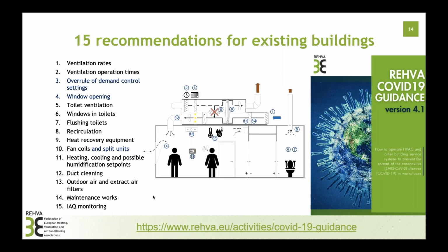REHVA has set out 15 recommendations, and these apply to the ventilation rates and how the ventilation is operated. Very many apply to the situation where you have a mechanical ventilation system, and in many countries this is implemented with heat recovery, and recirculation is not needed. That seems to be more of a European practice. But in the US, for instance, a lot of recirculation is used and heat recovery is not known. So the systems are different, and when it's natural ventilation, the guidance is also somewhat different.